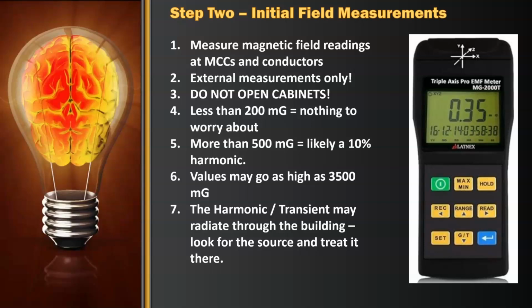When we look at this, we say, hey, we're going to put the correction inside the MCC. We do that because, number one, there's usually enough wire inside of there. Number two, I can put a label on the MCC and say, hey, there's something going on here. And number three, if an electrician looks at it, chances are he's probably going to understand what it is. If it's stuck inside a chiller panel, you never know about those chiller guys. They kind of do crazy things.